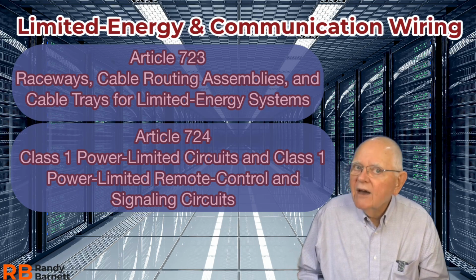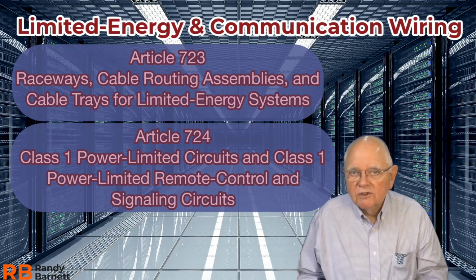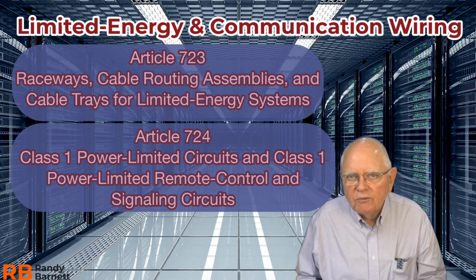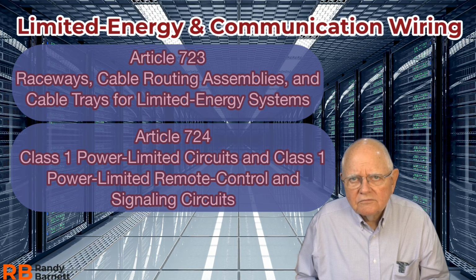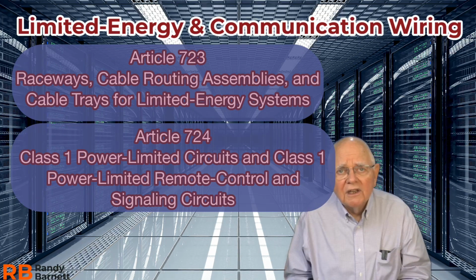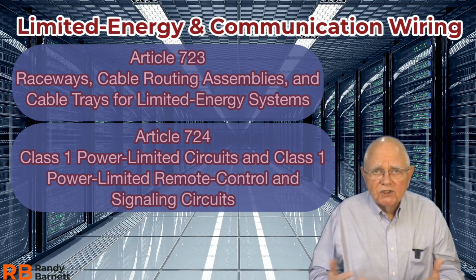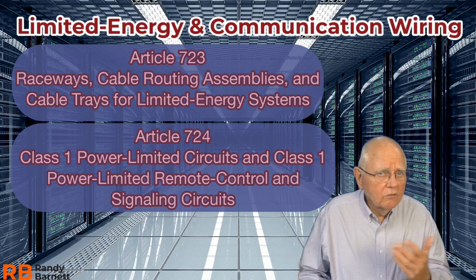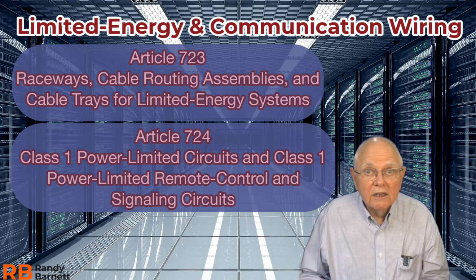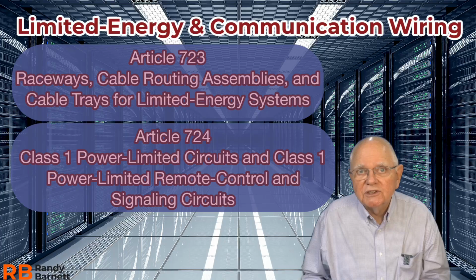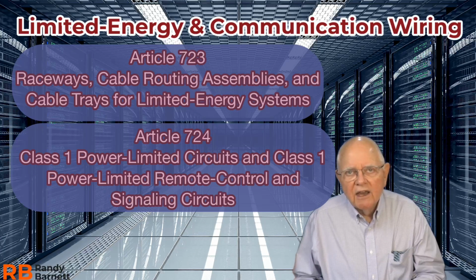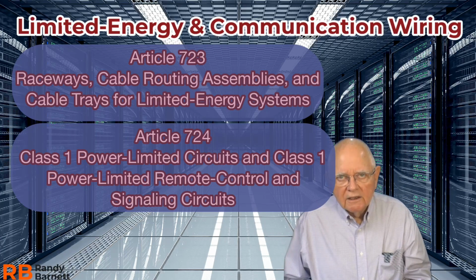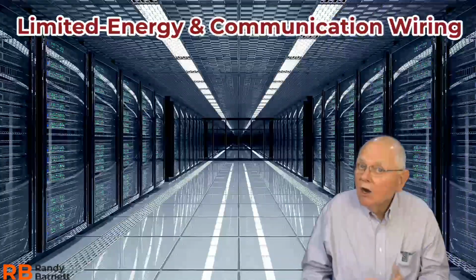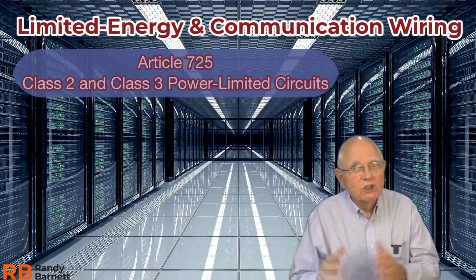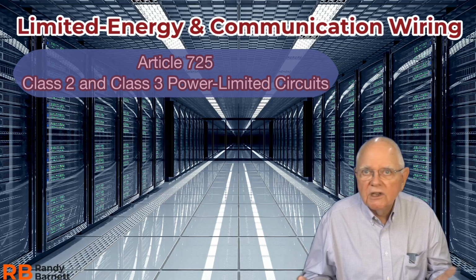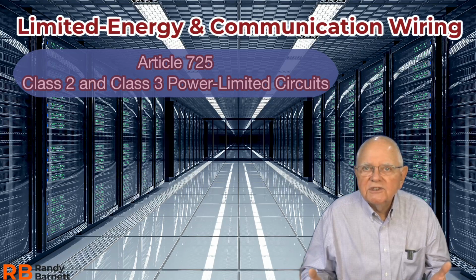Yeah, they are power limited, usually to 30 volts or less and 1,000 volt amps max, but they're not considered to really mitigate electric shock and fire, so they are not limited energy systems, Class 1 power systems. But nonetheless, there's now a new Article 724 that covers those Class 1 systems. Article 725, Class 2 and Class 3 power limited circuits. Very short. It's only 3 sections.